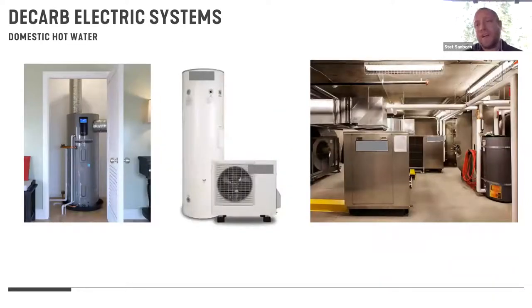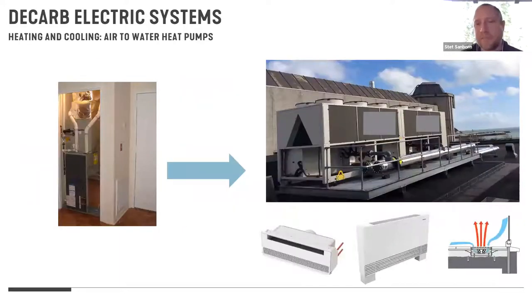The biggest move maker, I should go back, because one of the reasons that we see a lot of projects moving in this direction for air-to-water heat pumps, mini-split VRF, is they're looking for one appliance that does both things. They're looking for one set of equipment, they can buy it, and they can hot swap things out in the future as technology improves, rather than having a separate appliance or device that is for heating and then another one that's cooling. It can simplify our electrical connections and coordination if we have one central set of things that can do both.